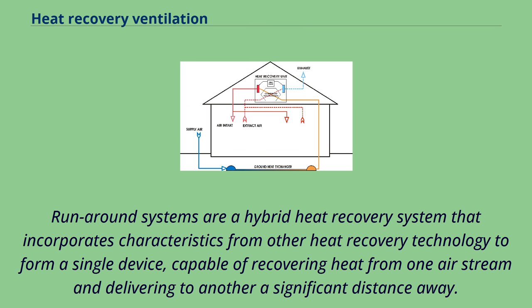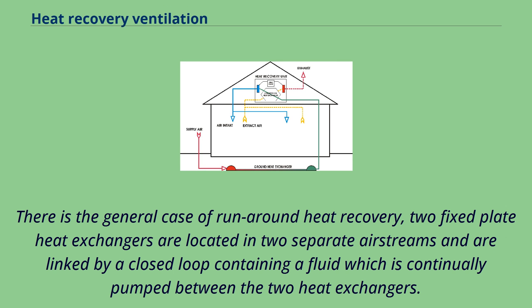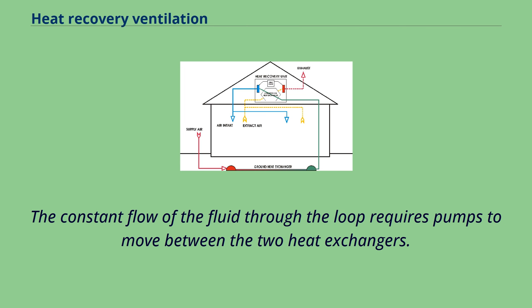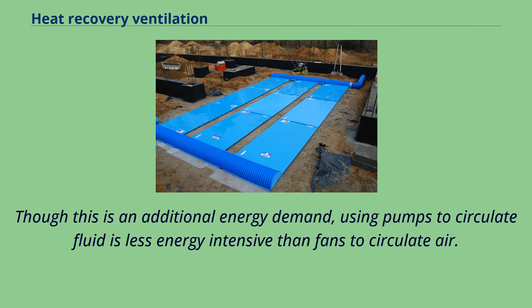Runaround systems are a hybrid heat recovery system that incorporates characteristics from other heat recovery technologies to form a single device capable of recovering heat from one air stream and delivering it to another a significant distance away. Two fixed plate heat exchangers are located in two separate airstreams and are linked by a closed loop containing a fluid continually pumped between them. The fluid is heated and cooled constantly as it flows around the loop, providing heat recovery. Though pumps create an additional energy demand, circulating fluid with pumps is less energy intensive than using fans to circulate air.